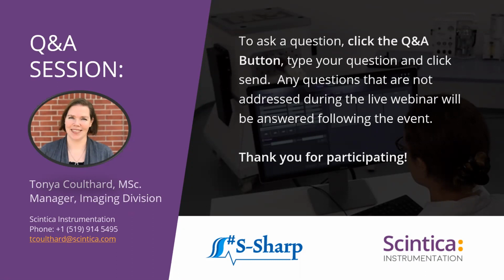So we would chat with you about your research, understand the structures that you want to image, because again, as frequency increases, resolution increases, but depth of penetration decreases. So if you're imaging rats, you're typically going to go with a 20 megahertz probe so you have deeper penetration to be able to see the structures of interest. However, if your rats are all using subcutaneous tumors, then you don't need the depth of penetration. So it really comes down to a conversation to make sure that we do configure the system to work appropriately for the models that you're working with. If your research focus changes and a different probe would be better, those can always be added on after the fact. So it's not that the system is locked with the probes that you purchase.